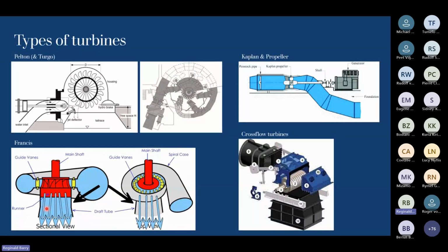Then on the top right, which we have many of in South Africa and in Africa as well, is your low head Kaplan and propeller installations. And there are, again, many configurations. This is called the S type. So you've got a shaft that goes through the draft tube with a bearing house here. And that shaft goes into the runner itself. And in a Kaplan, the guide vanes and the runner blades can turn, and so you can control and regulate the flow.